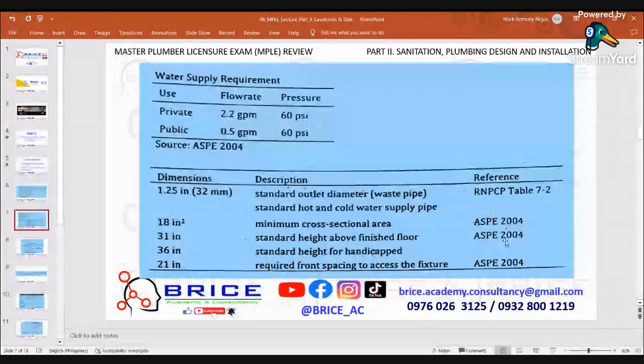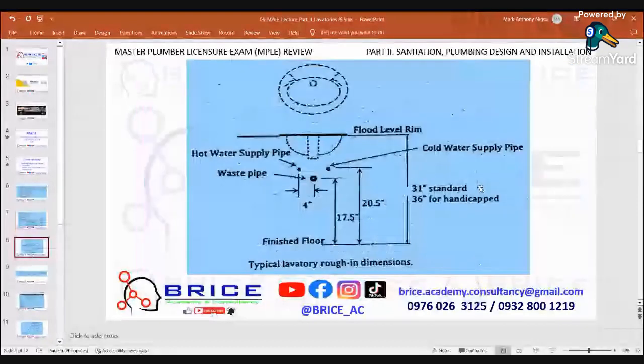These are the typical lavatory rough-in dimensions. The flood level rim is the highest point of the lavatory. The hot water supply pipe is on the left and the cold water supply pipe is on the right. The waste pipe is 17.5 inches above the finish floor line, 20.5 inches to the cold water supply, and 31 inches standard height — 36 inches for handicap.